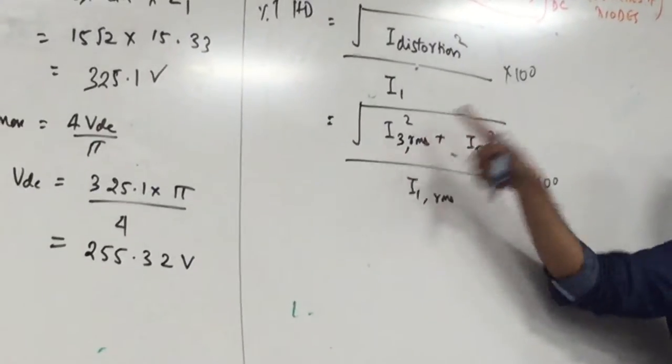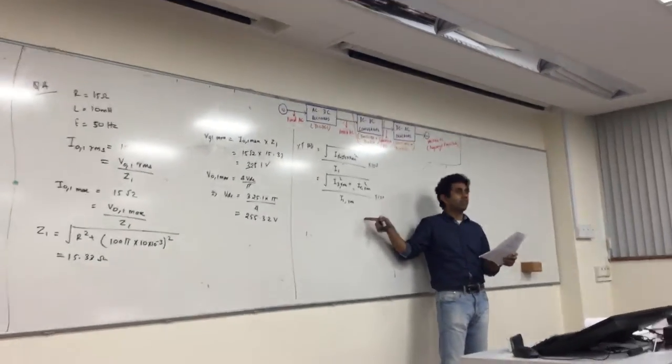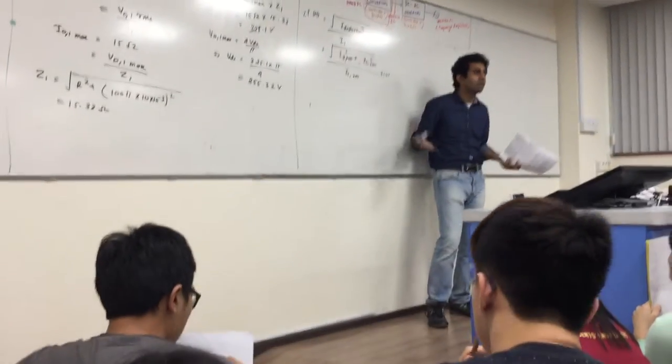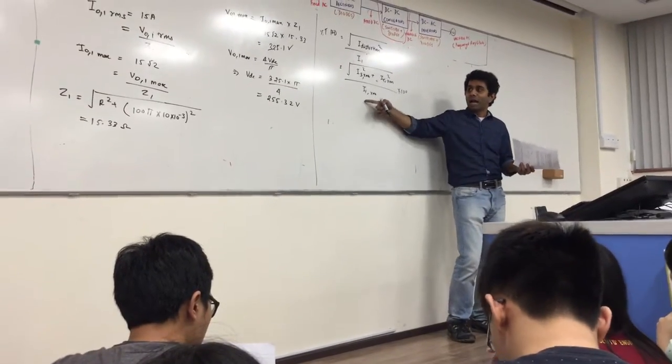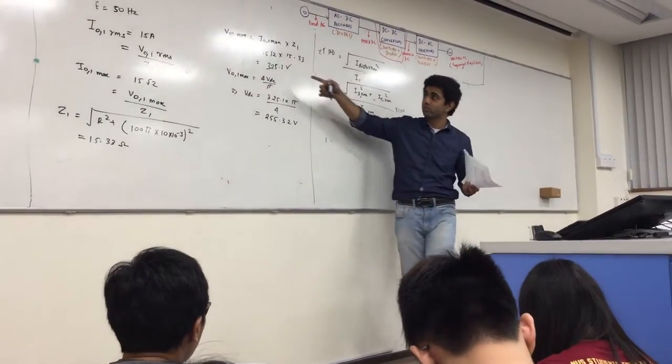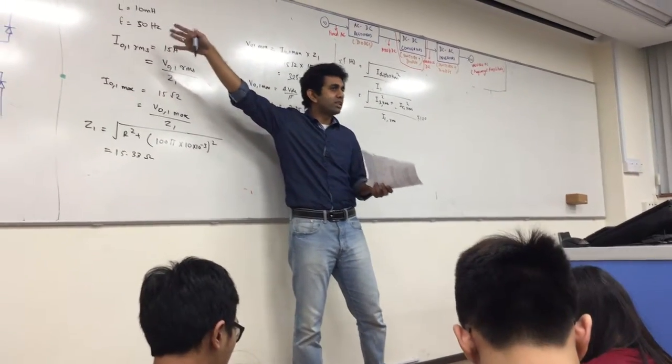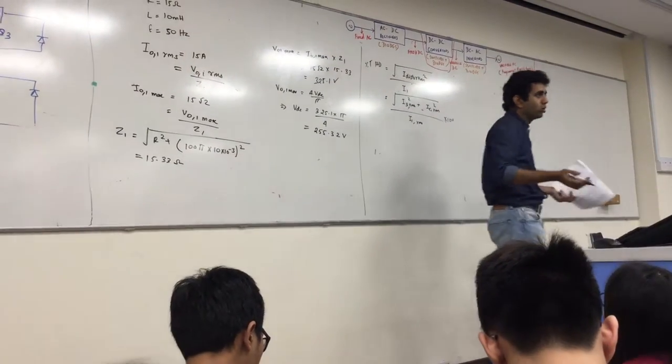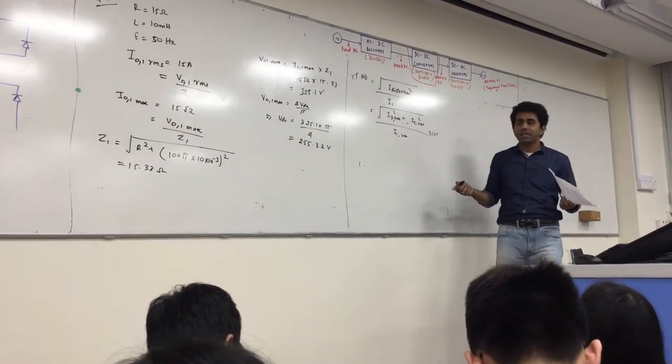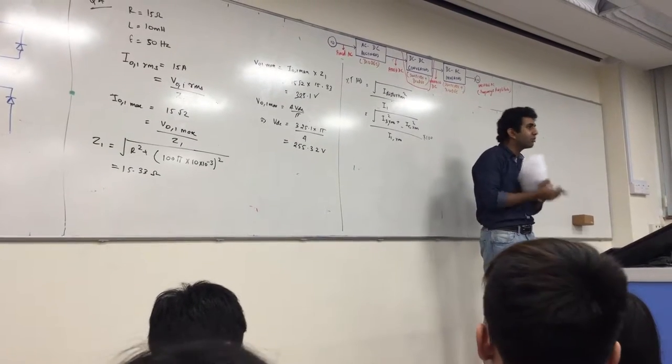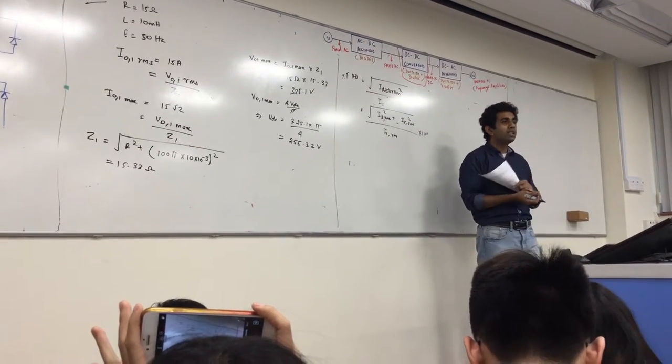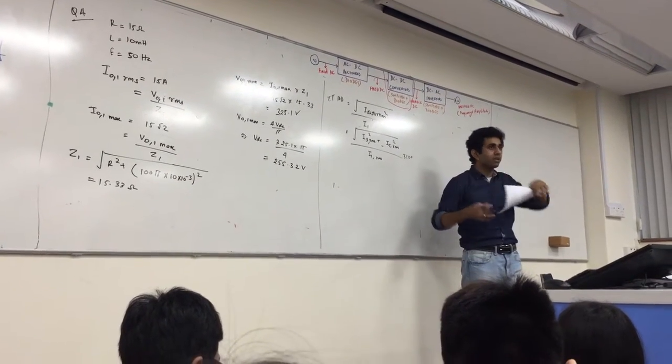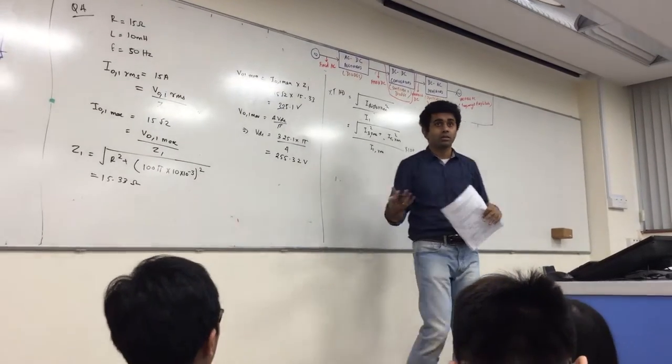These are all in RMS values, so I distortion square is going to be I3 RMS square plus I5 RMS square, by I1 RMS. You're going to have the distortion now - in our case, it's just a 3rd and a 5th harmonic. But I can find out V3 RMS, V5 RMS, I can find out Z3 and Z5, and then I can correspondingly find out what is my I3 RMS and my I5 RMS.